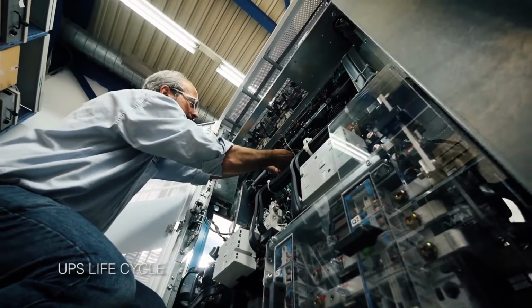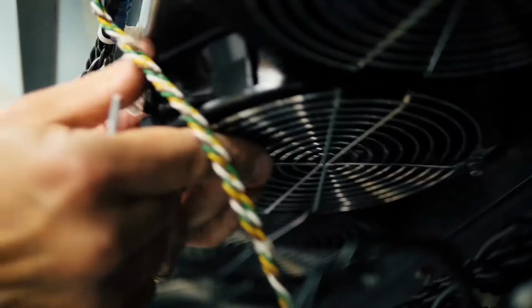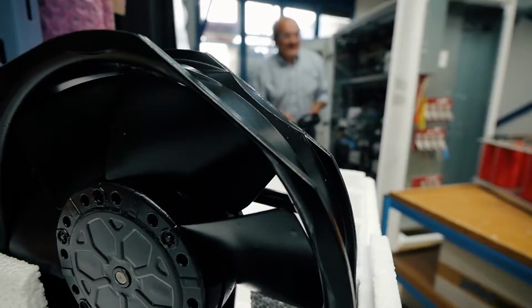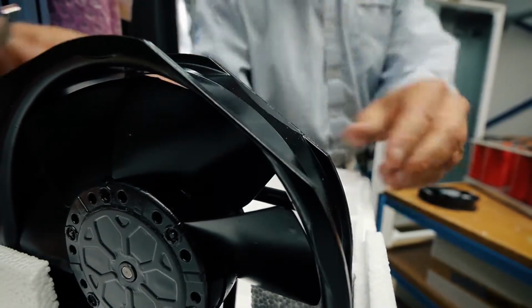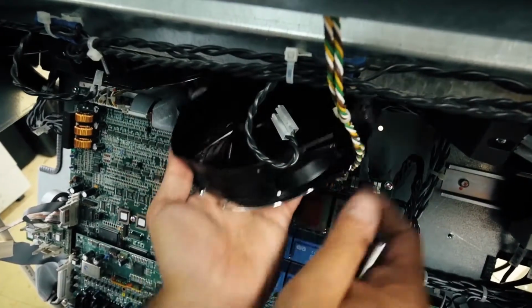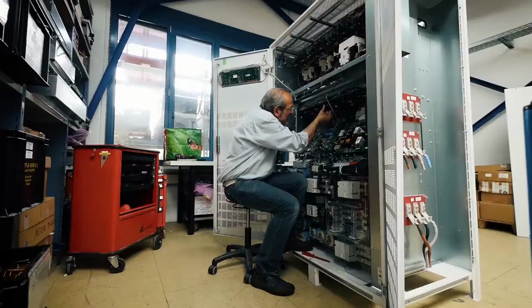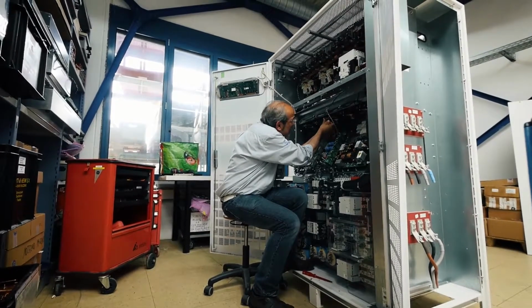The average UPS life cycle is 10 to 15 years. During this period, the device undergoes maintenance several times. After 2.5 years, the cooling fan is changed. After 5 years, the battery. After a further 2.5 years, the cooling fan is changed again.